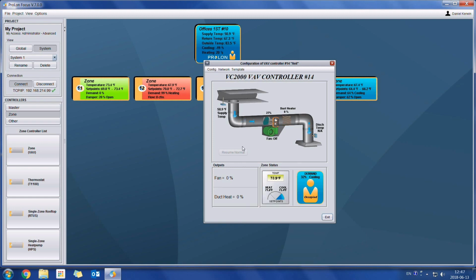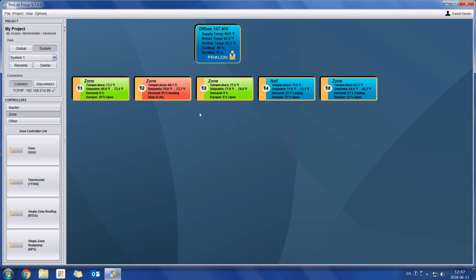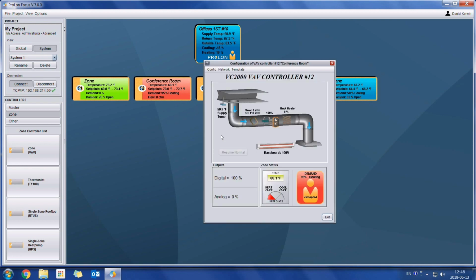What we've been seeing here is a pressure dependent VAV controller. This type of VAV controller does not have a flow sensor on it. If we did want to look at a pressure independent model, where we are actually measuring the actual flow into the space, I can just go take a look at the one which I have right here. And so right here we can see our flow sensor.